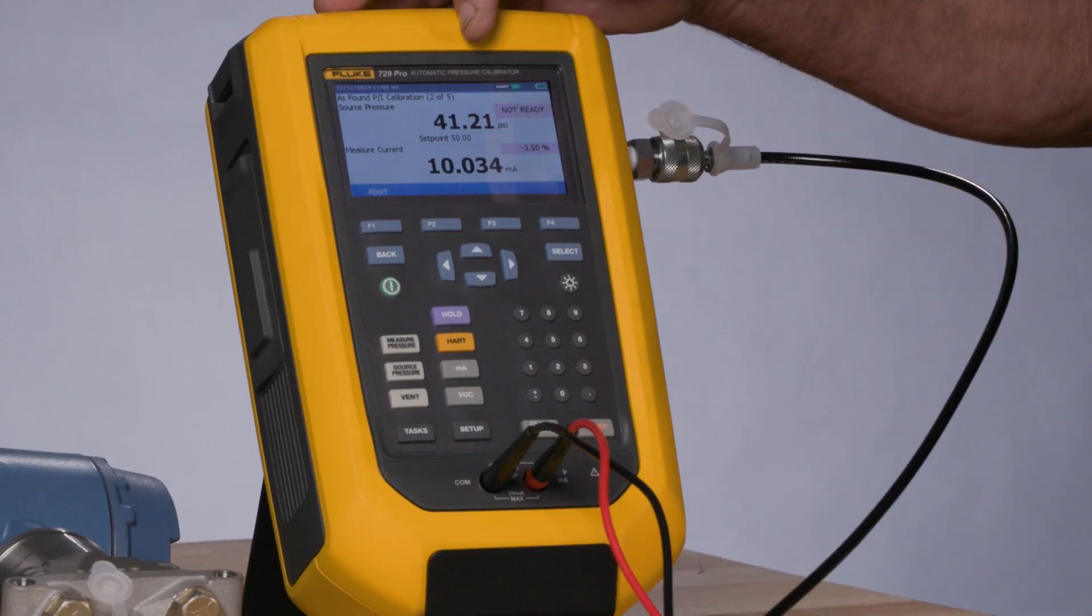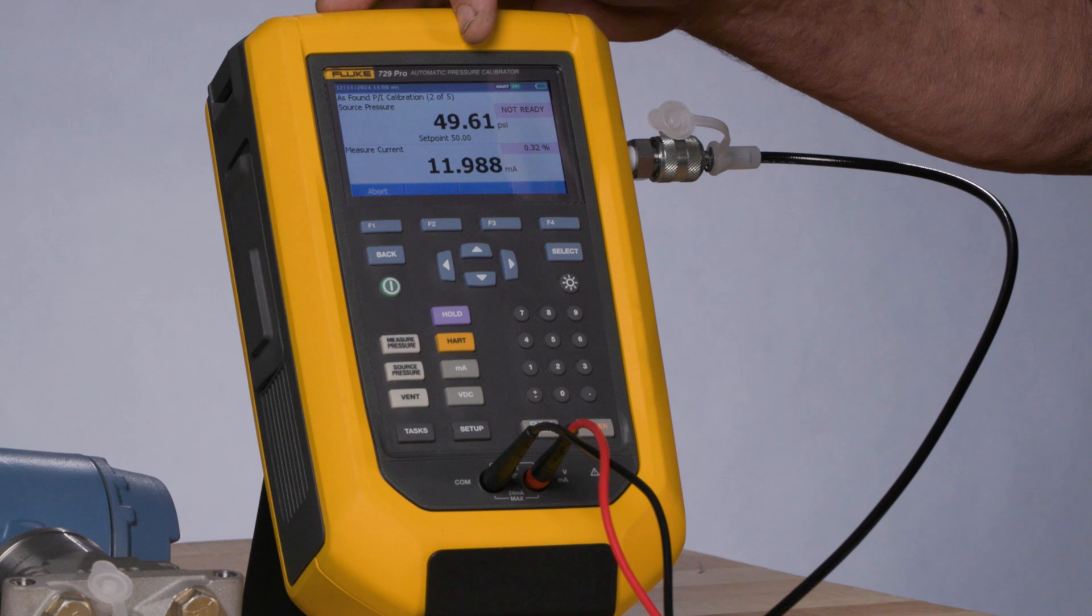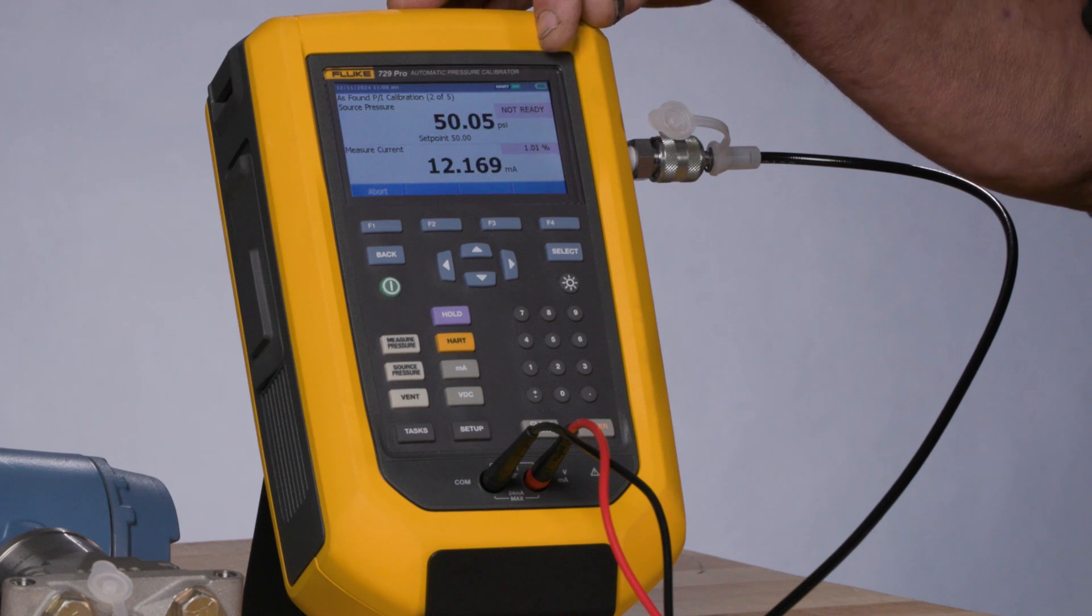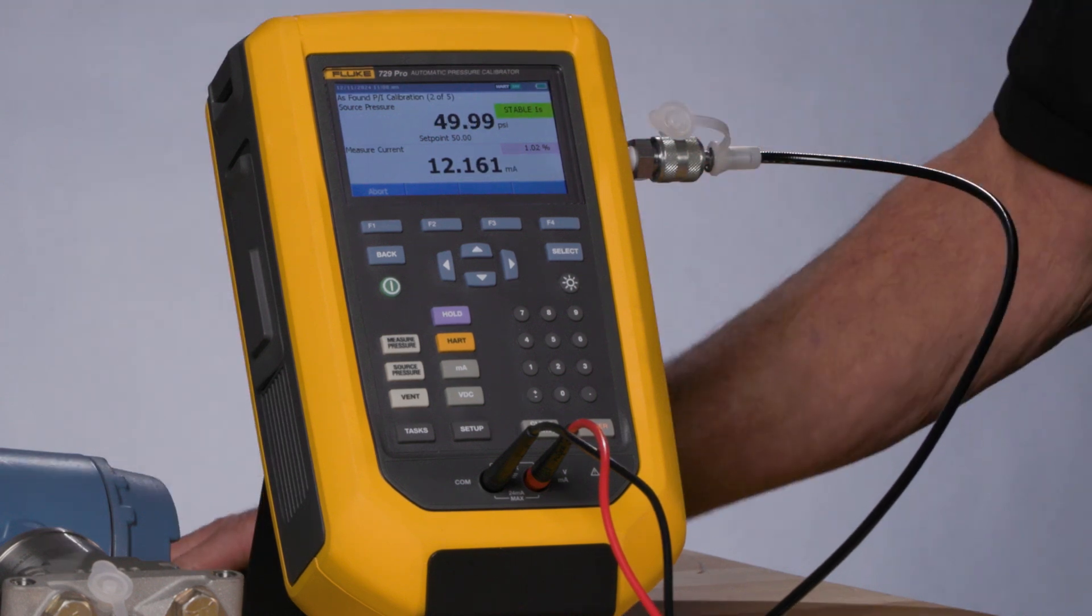Right now we're going to the first test point at 50 psi, once it gets within 10 points, you'll see it shows stable, and after 5 seconds, it'll then go to the next point, which is 100 psi.